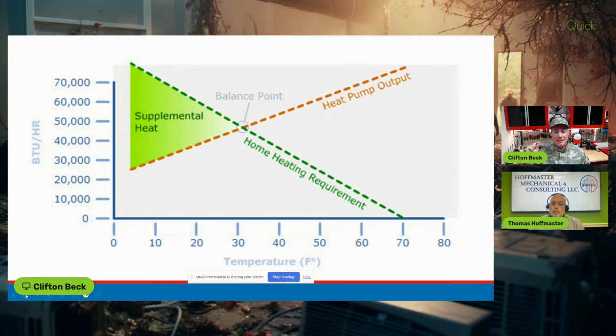Most people, right? But if we look at the heat output, we have to look at the descending capability of the heat pump, not just the BTUs it can provide, but the energy consumption we're producing. We have to look at the COP, the coefficient of performance, to see how many BTUs we're using and reducing, because at some point it's more economical to use a secondary energy source, whether electric resistance heating or gas fuel. We have to look at what that balance point is and how much comfort we're willing to sacrifice to maintain the most fuel efficient opportunity.